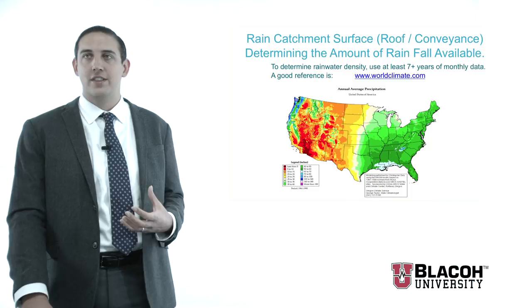How the rainfall comes in is also determined by geography. In the northeast, we tend to get fairly consistent precipitation events. In the Pacific Northwest, the majority of rain is mist — not heavy rainfall — and misting is very hard to capture from a rainwater reclamation standpoint. In the Gulf region, the majority of rain comes in very quickly. They have what's called thunder boomers, where you can see precipitation events going four to five inches an hour. This is going to largely skew your ability to capture that rainfall and cause a lot more runoff. So geography, in addition to total rainfall, does have an overall impact on your system design.